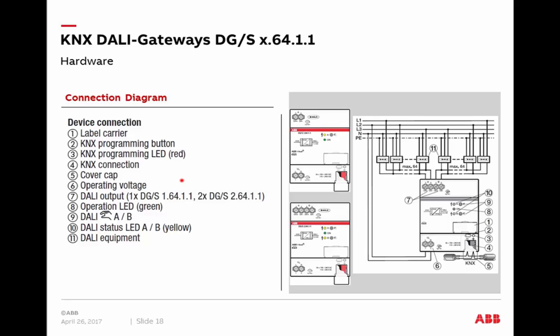A look at the hardware: the connection diagram for the two-fold device shows two independent channels, each connecting up to 64 DALI ballasts, with the DALI power supply, KNX connection, LEDs, and in this case two push buttons. One function of the push buttons is manual operation; the second is to start DALI addressing if necessary, by pressing longer on the button.